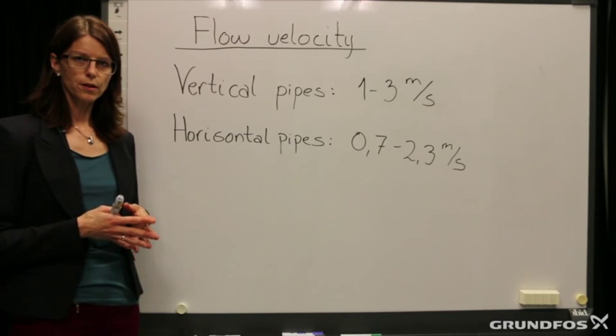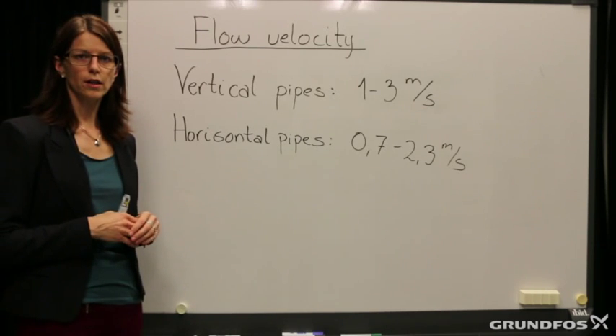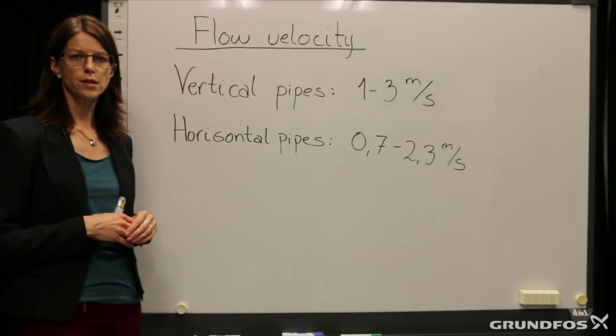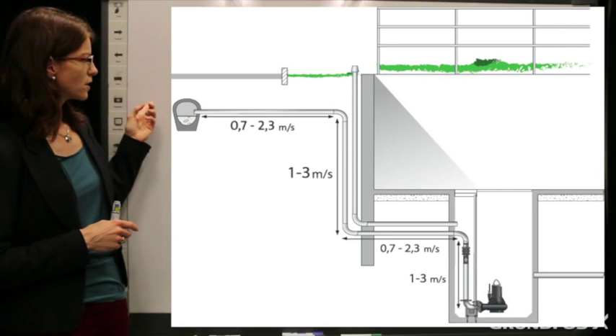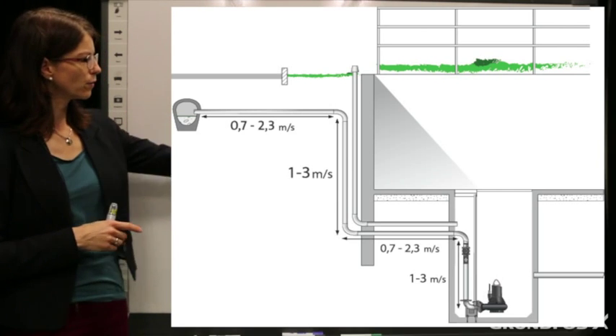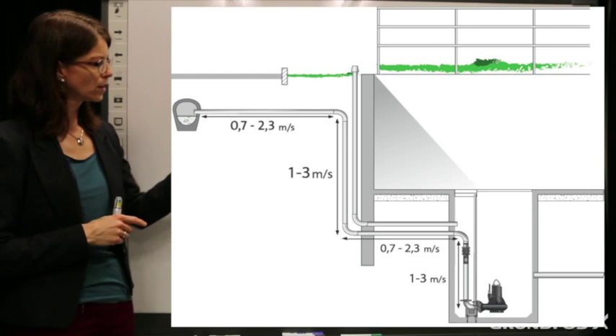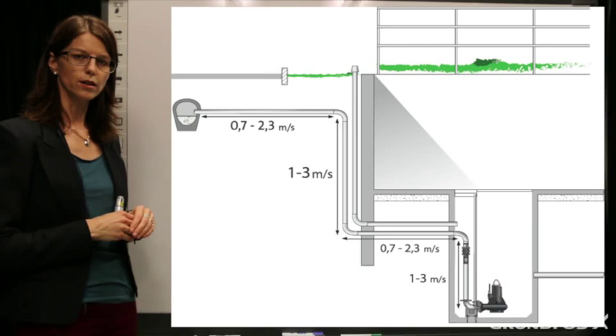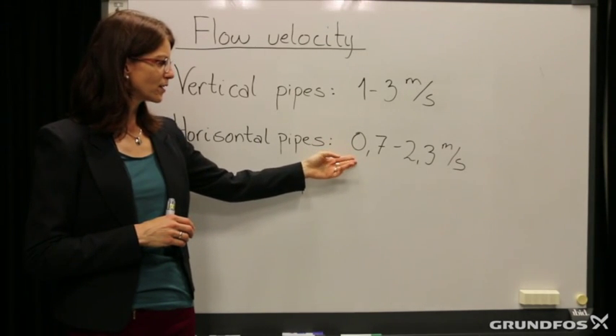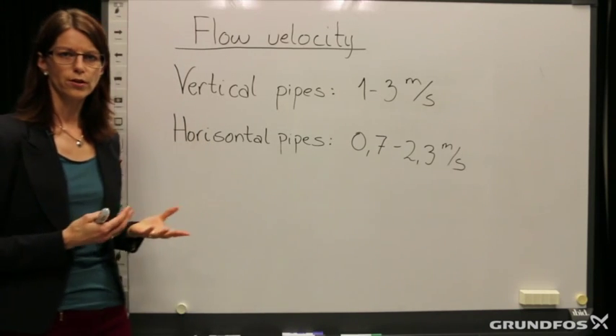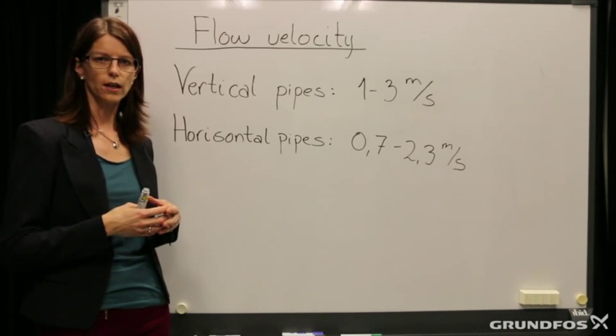When we talk about the pipes and the dynamic head, we also need to talk about the flow velocity. It is a very important factor when dimensioning the pipe system for a wastewater installation. The recommended velocity for vertical pipes in the pit is 1 to 3 meters per second, and for horizontal pipes in the ground, 0.7 to 2.3 meters per second. The reason why 0.7 meters per second is recommended is to avoid sedimentation — solids staying in the pipes that can cause clogging.